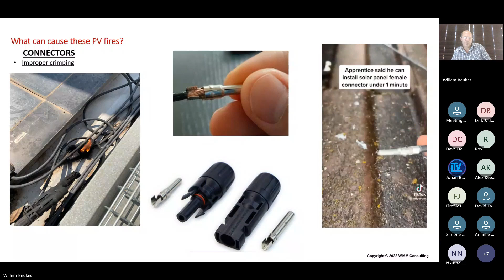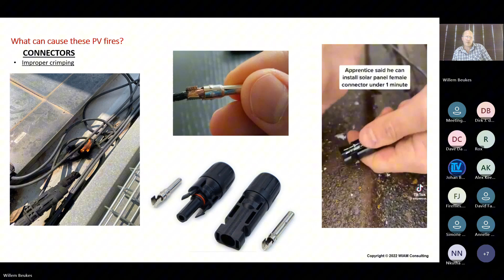Now, that wire must not extend past the wings of the site, and also the equipment used to crimp, that is also not the right equipment to crimp the tube to the wire. You have to have an MC4 crimp and make sure you have positive connection on the wire and on the tube. And that's where most of these connectors cause fires on systems not being done correctly.